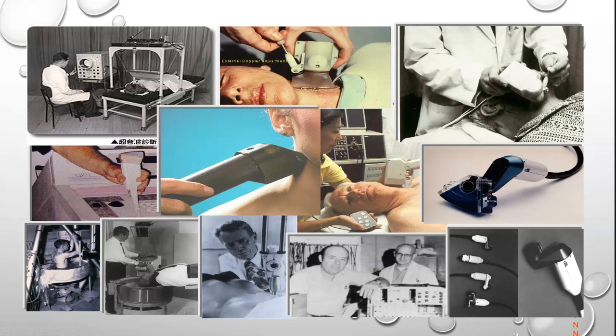So these are all the different transducers we've utilized in ultrasound over the years. This is an old Doppler transducer which has two elements. This is the Doppler one over here, and this is the imaging element here. It's kind of a unique transducer.